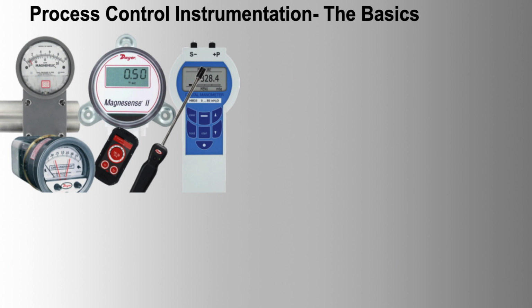4. Installation location. Proper placement is essential to avoid interference from tank structures or turbulence. 5. Redundancy and reliability. Implement redundancy in critical level measurements for safety and reliability. 6. Calibration and maintenance. Regular calibration and maintenance are necessary to ensure accuracy and reliability. Safety considerations. Ensure that level instruments are suitable for use in hazardous areas and can handle overfill or low-level conditions.